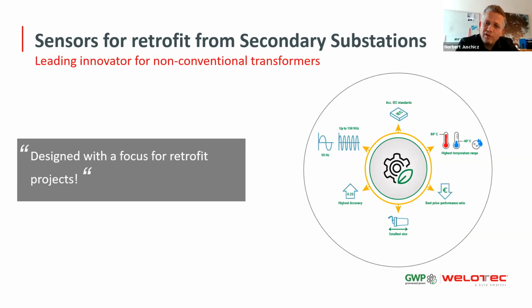They want to cover most use cases, or as many as possible. For this reason, it's always a good idea to have sensors on hand according to the highest accuracy class: 0.2 S for current sensors, or 0.2 for voltage sensors.